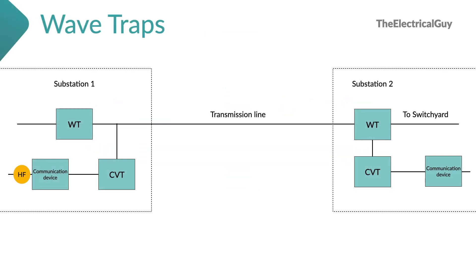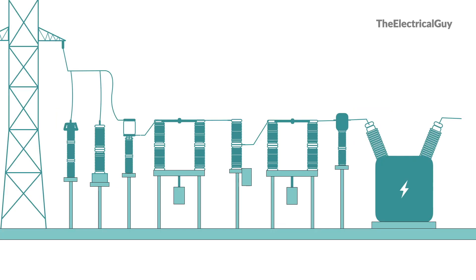For instance, a high frequency communication signal coming from substation 1 will travel via the transmission line to substation 2. Now this signal will try to enter the switchyard. However, the wave trap will block this signal. The signal will then look for another path, and that path would be from the CVT or coupling capacitor to the communication device. This is how wave traps work and why they are really important.